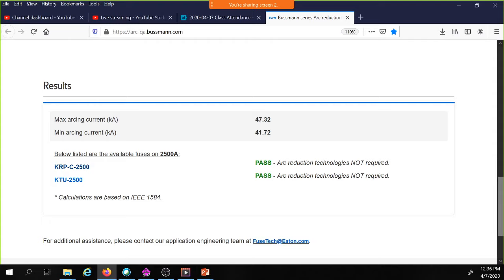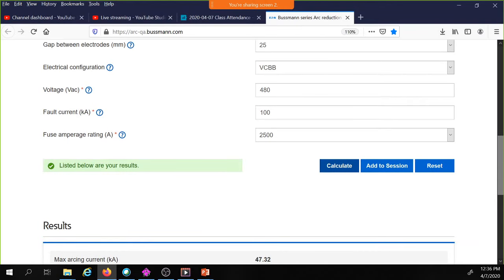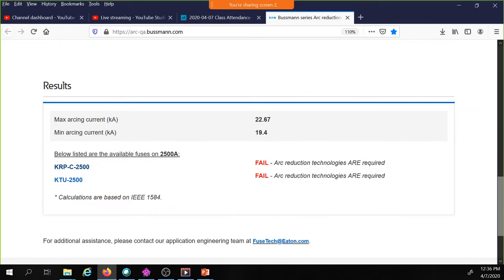It's arc-qa.bussmann.com. Very important. I would bookmark this. You can, again, add to session. You can make changes up here. You can say, well, I'm at 208 volts. You can do 208 volts and recalculate that same number. And now that 2500 amp fuse fails. Now you need an arc reduction technology because your arcing currents are way lower than what they were before. My minimum is only 19,000 amps at 208 volts.